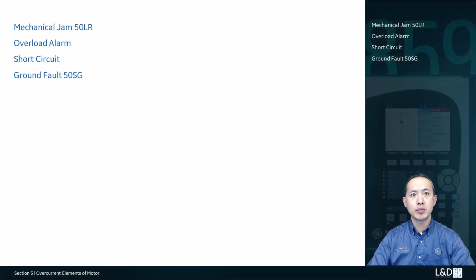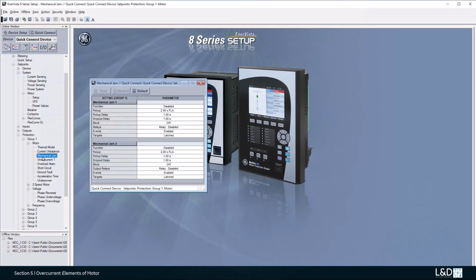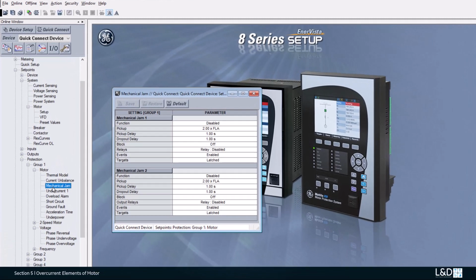In this overcurrent section, we'll cover only the overcurrent elements under the motor settings: mechanical jam, overload alarm, short circuit, and ground fault. These are all the available overcurrent elements in the 859 basic order code. If the order code is advanced, then a new current elements group will be available to use. The mechanical jam setting should be set below the overload curve but above any normal overload conditions of the motor. The main purpose of this mechanical jam element is to protect the driven equipment from jammed or broken equipment.